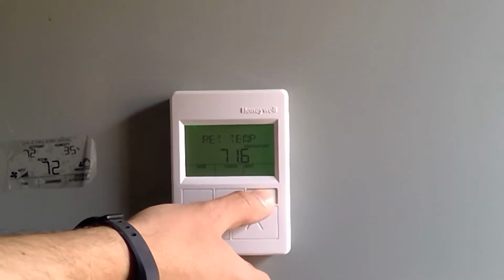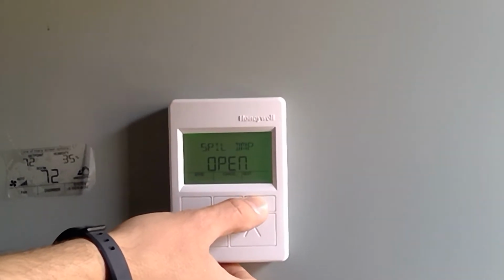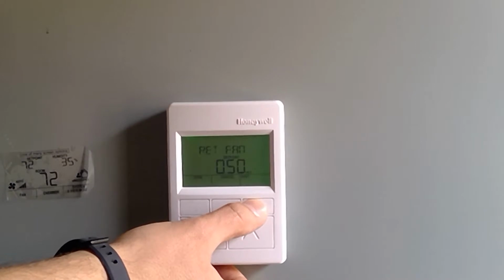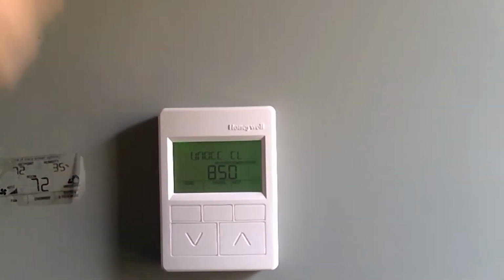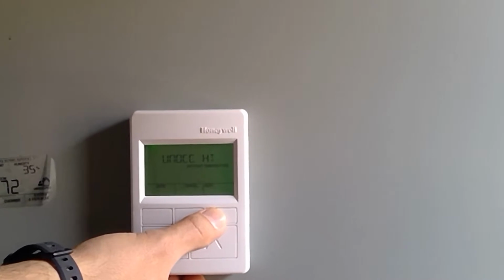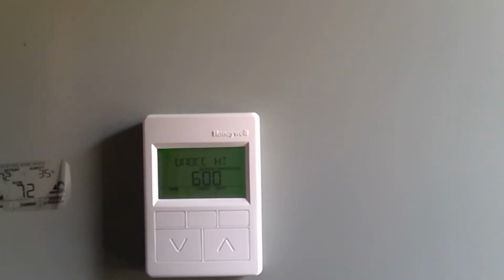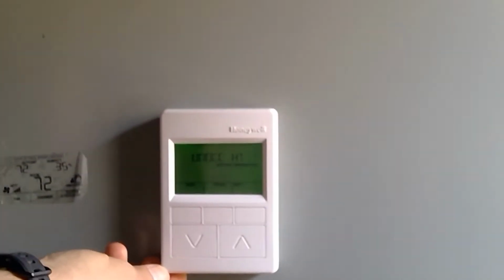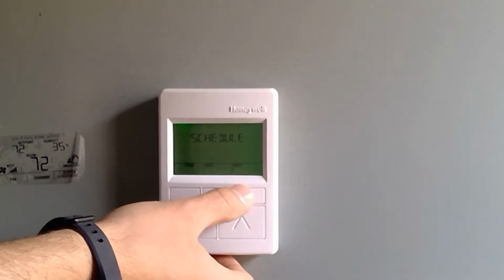Yeah. So it timed out already, so I'm just going to scroll back to where we were. Cooling, heating, outdoor air, return fan, unoccupied cooling set point. This is your return set point, so when it's off at night, if the return goes above 85 in the cooling mode, it'll kick the unit back on. And then in the heating mode, if it goes below 60 on the return space temperature, it's going to kick on. Yep. Okay. And I think that was it.